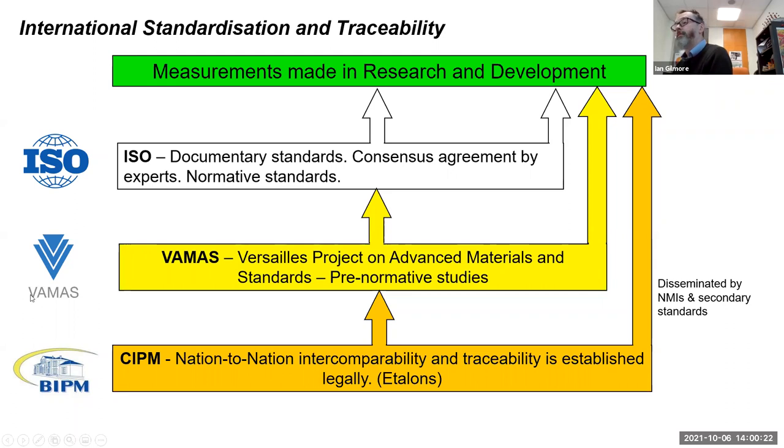These are very complex instruments, and each variable that isn't set correctly could lead to erroneous results. In my lab over many years we've been trying to unpick those issues and map them so that users can set the instrument into the most reliable space to get repeatable and reproducible results between different laboratories. In our community we have a structure for this: the CIPM in Paris provides nation-to-nation intercomparability through reference materials going between national metrology institutes, giving the highest level of accuracy — though these aren't always directly relevant to research environments.